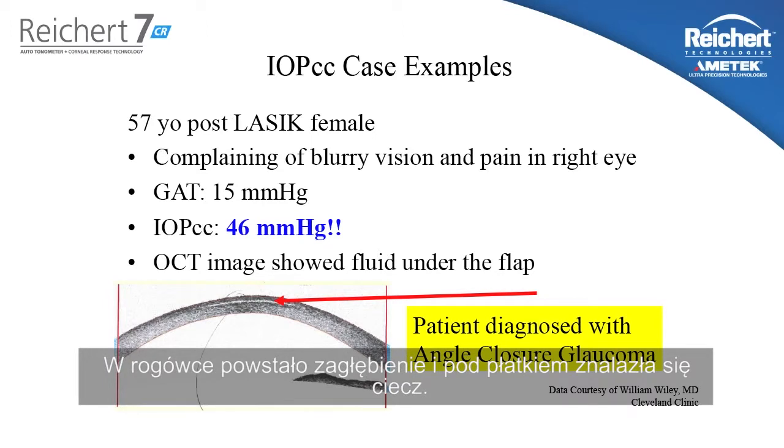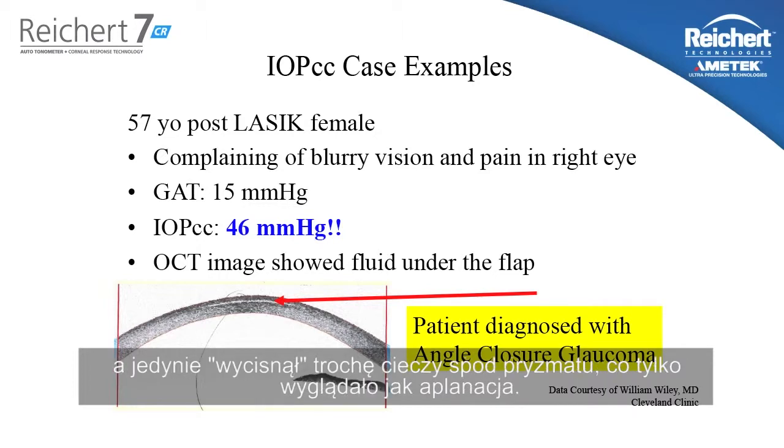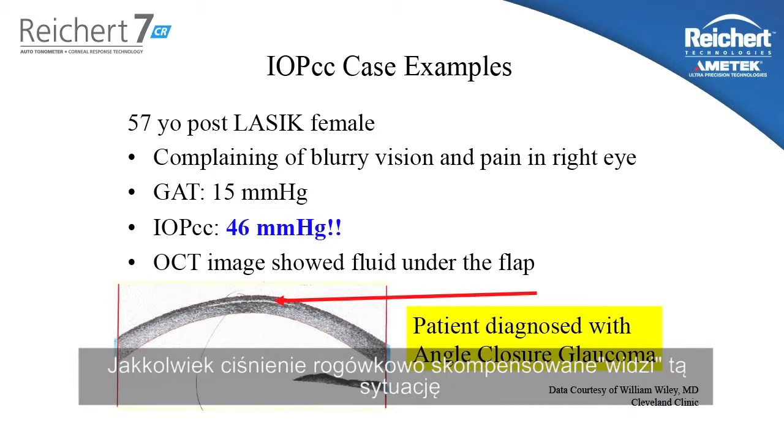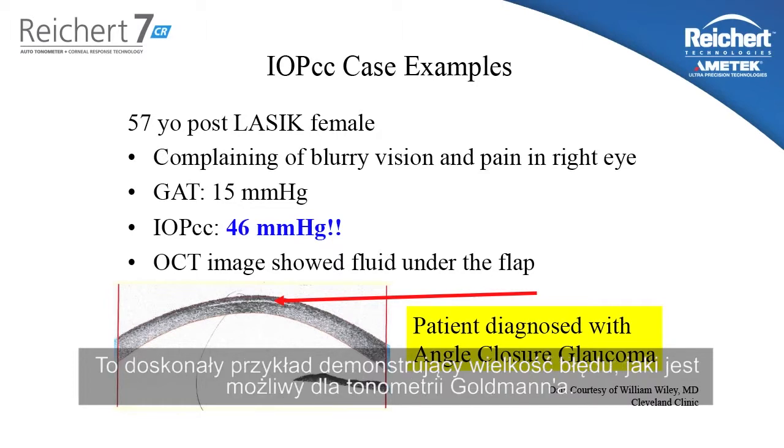This woman had an angle closure glaucoma attack causing the pressure to spike severely. The cornea became edematous and water got trapped in the LASIK flap. The Goldmann tonometer really didn't applanate the cornea — it just displaced some of that free water and it looked like an applanation. However, the corneal compensated pressure measurement sees through that because it understands the properties of the cornea and gives you a truer pressure measurement. This is a great example of the magnitude of error that can be possible with Goldmann tonometry.